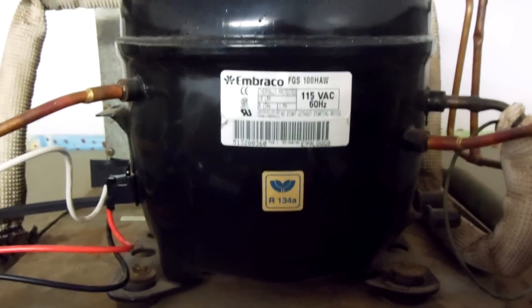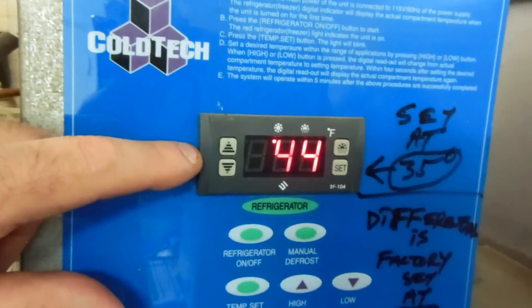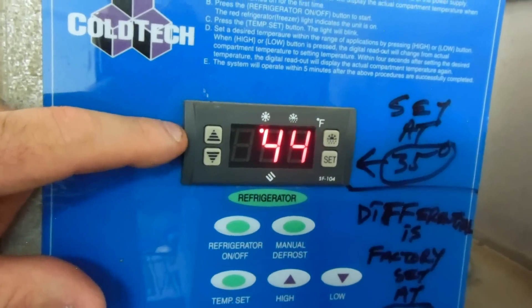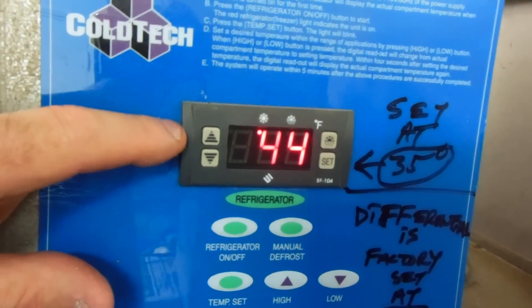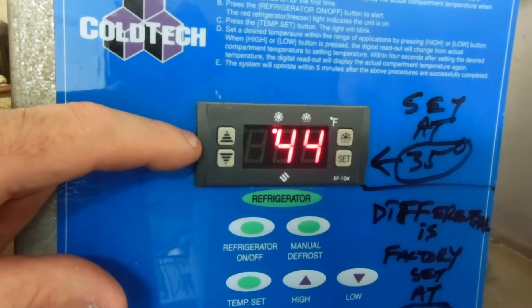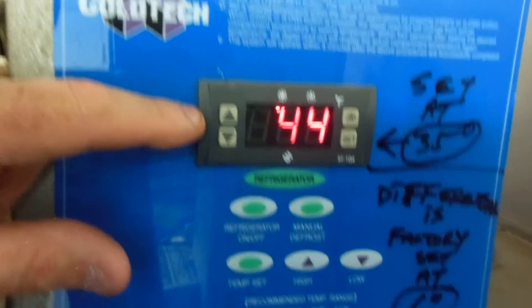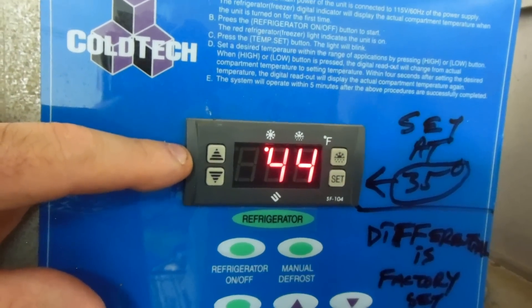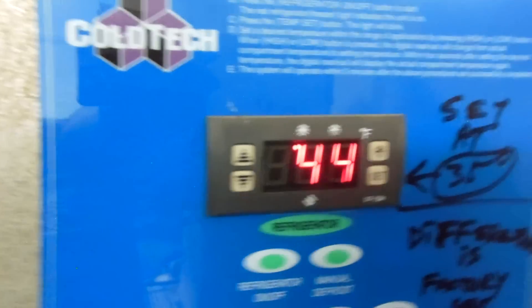You can tell from the little tag on the bottom it's starting to get a little warm. She was having trouble starting, and it has only a two-minute off cycle. I tried to adjust it but it won't let me - I can't adjust the E4 parameter on this SF104 controller. NorCal refrigeration, Rasta, if you know how to unlock that off-cycle setting, let me know.